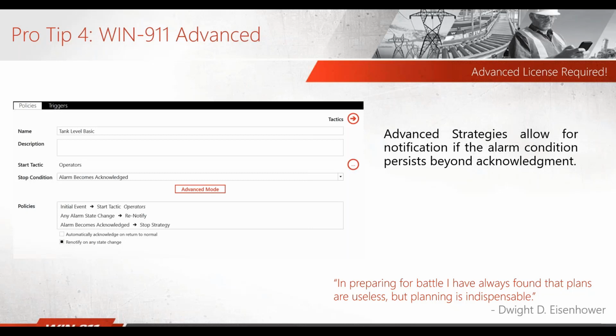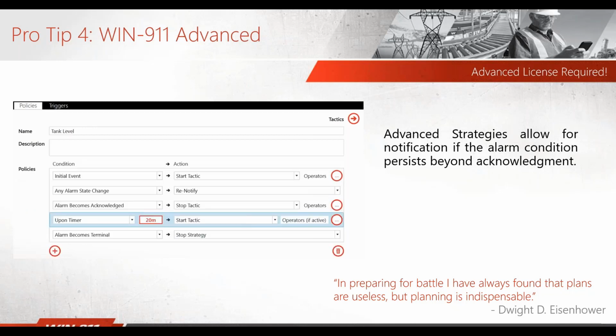So with version 7, we received a lot of requests that if an alarm becomes acknowledged and it doesn't transition to inactive, they still would like to notify operators about that. You can do that with advanced strategies. For example, you can set up a timer that says after 20 minutes, if an alarm is still not terminal, which means it's not inactive, go ahead and start a tactic and re-notify some operators that, hey, this alarm is still active. It's been acknowledged, but it's still active and it's still a problem.